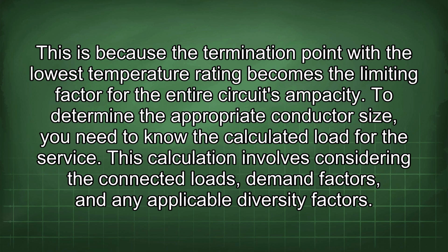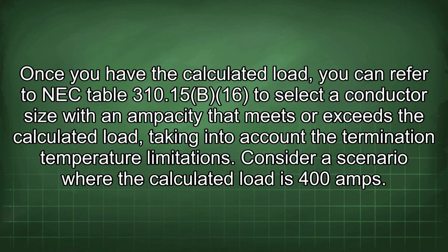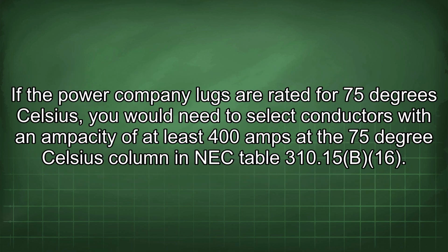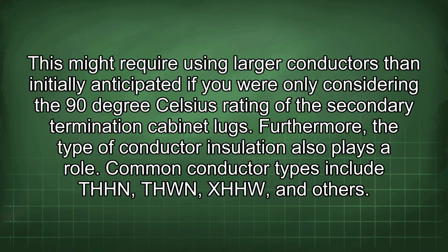To determine the appropriate conductor size, you need to know the calculated load for the service. This calculation involves considering the connected loads, demand factors, and any applicable diversity factors. Once you have the calculated load, you can refer to NEC Table 310.15(B)(16) to select a conductor size with an ampacity that meets or exceeds the calculated load, taking into account the termination temperature limitations. Consider a scenario where the calculated load is 400 amps. If the power company lugs are rated for 75°C, you would need to select conductors with an ampacity of at least 400 amps at the 75°C column in NEC Table 310.15(B)(16).